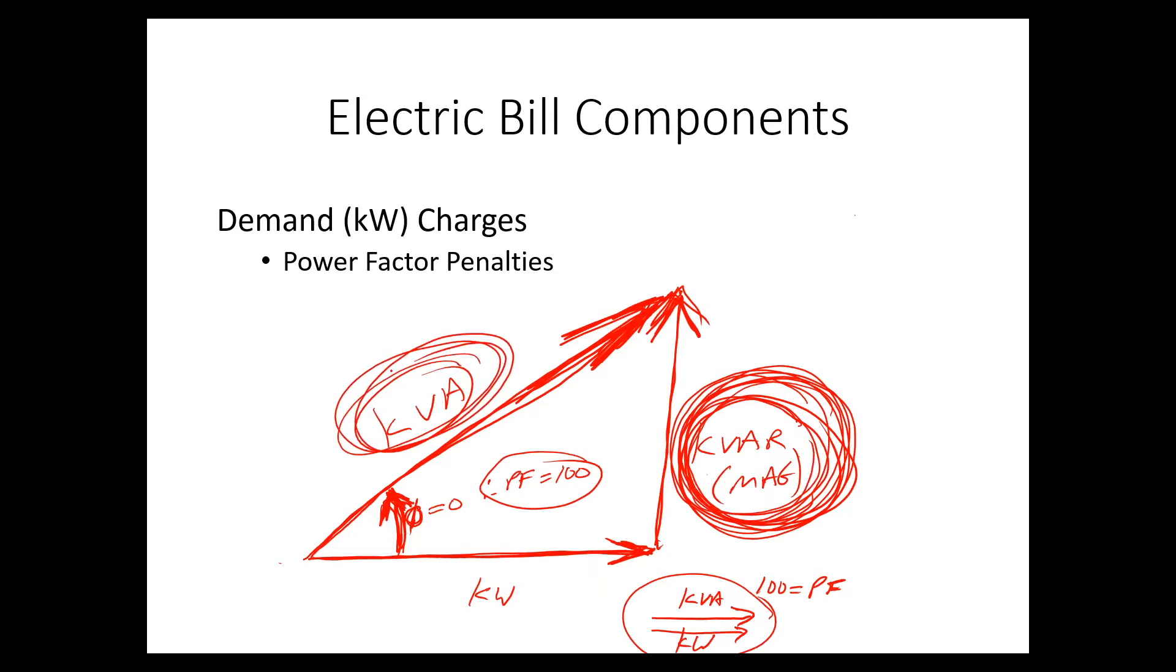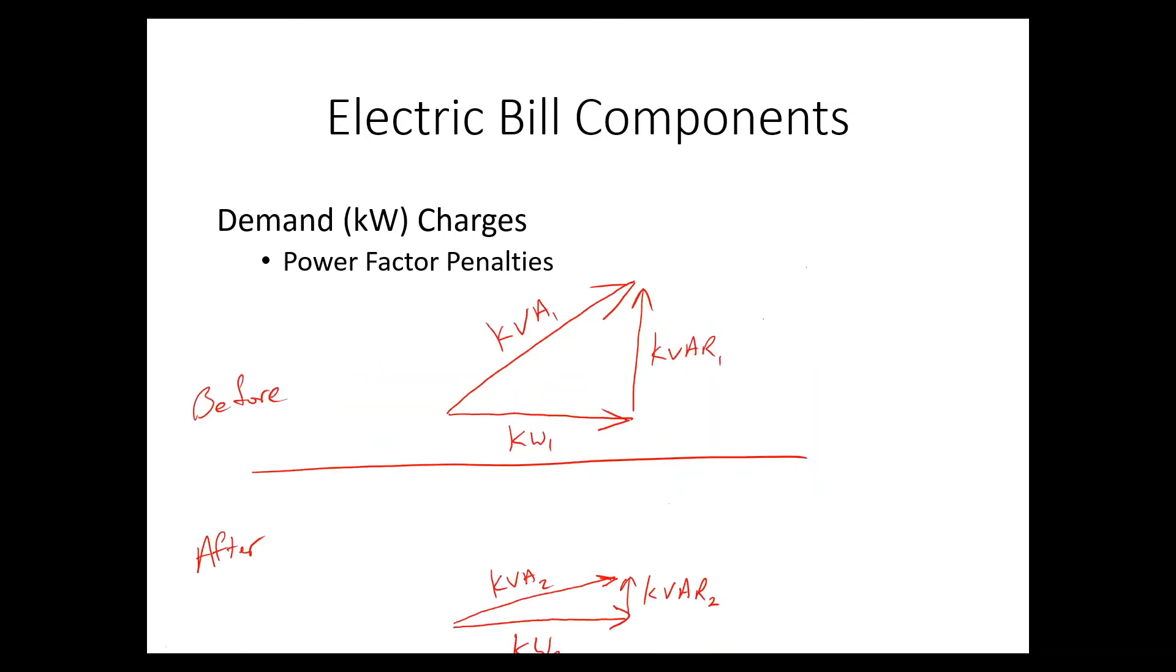Let's take a look at a couple of examples. Consider the before case, which is the diagram on top, and you have a situation where phi is not zero, your power factor is not 100%, let's just say it's around 70, okay, say power factor equals 70. The utility is having to provide a lot of KVA so that you can do a certain amount of work at KW.